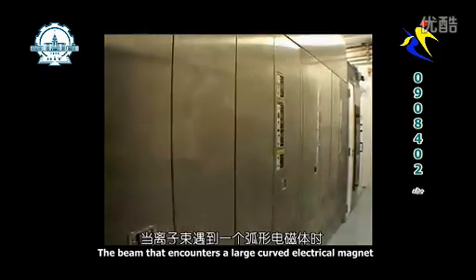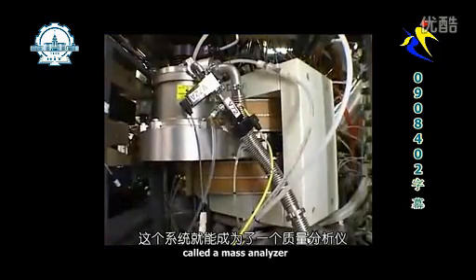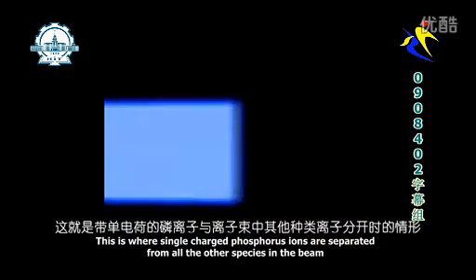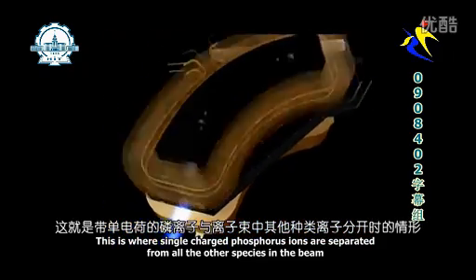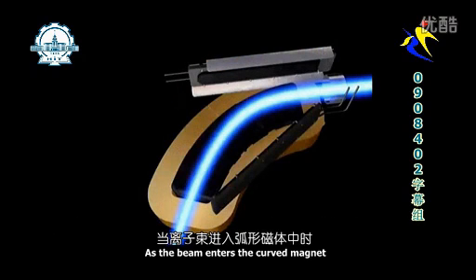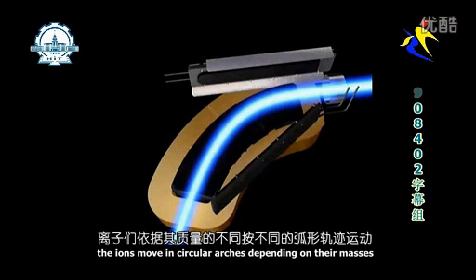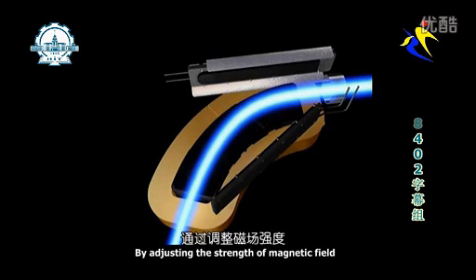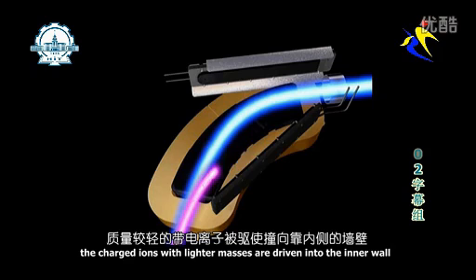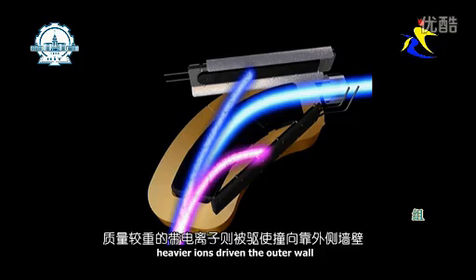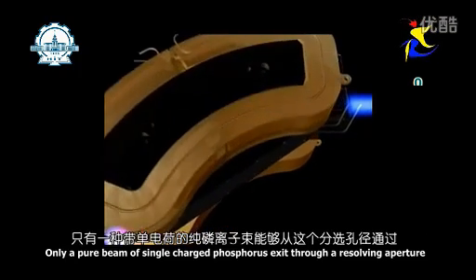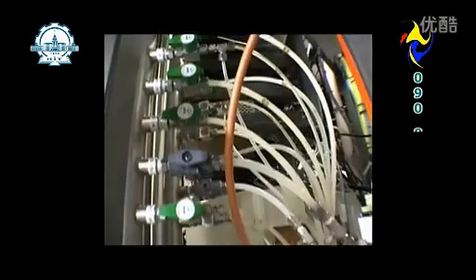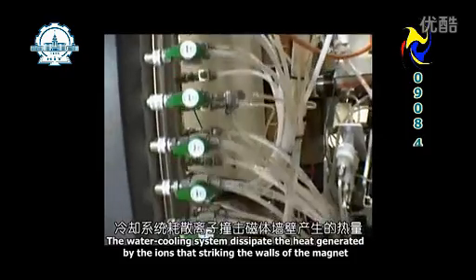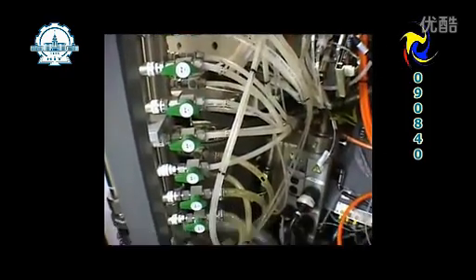The beam then encounters a large curved electromagnet called a mass analyzer. This is where single-charged phosphorus ions are separated from all the other species in the beam. As the beam enters the curved magnet, the ions move in circular arcs, depending on their masses. By adjusting the strength of the magnetic field, the charged ions with lighter masses are driven into the inner wall. Heavier ions strike the outer wall. Only a pure beam of single-charged phosphorus exits through a resolving aperture. The water cooling system dissipates the heat generated by the ions that are striking the walls of the magnet.